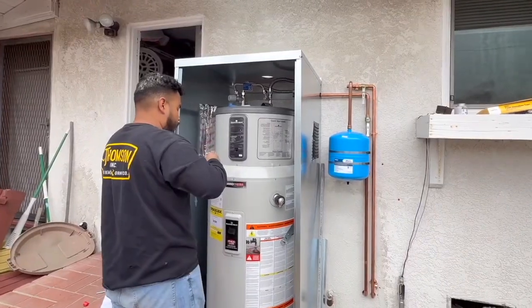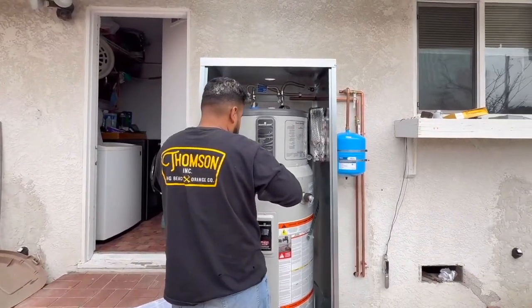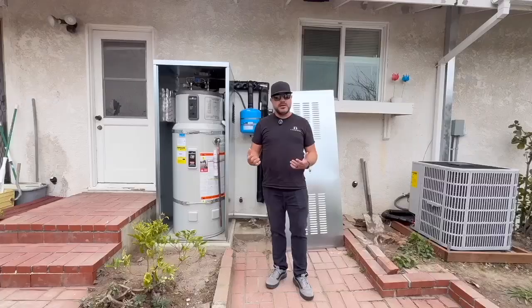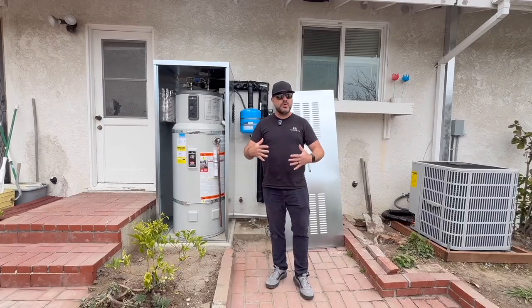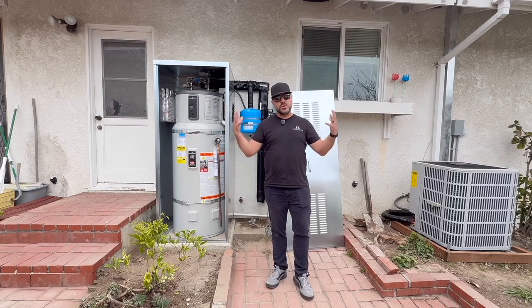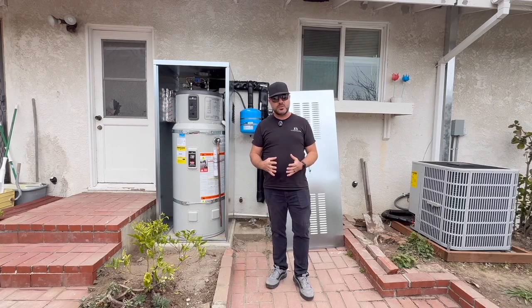Even if it's cold outside, a heat pump is still engineered to absorb heat from the air. Us as warm-blooded mammals may feel cold - we may be sensibly chilly - but there's still plenty of heat in the air that can be absorbed by the refrigerant and transferred into the water.